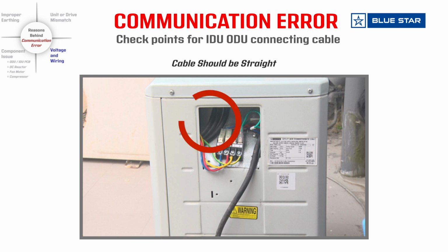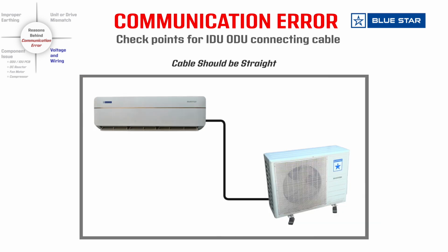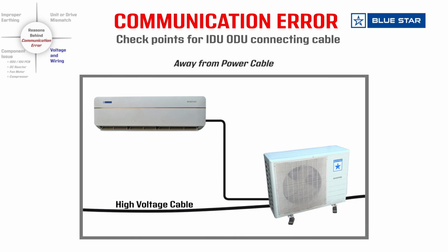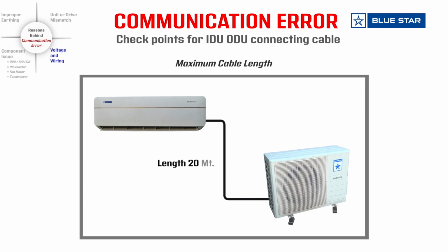It should be straight and there should not be any windings. The cable should be away from high voltage cable, that is, 3-phase supply. In case it is unavoidable to pass the power cable nearby, then there should be 1 foot distance between them. Length of the cable should not be more than 20 meters.